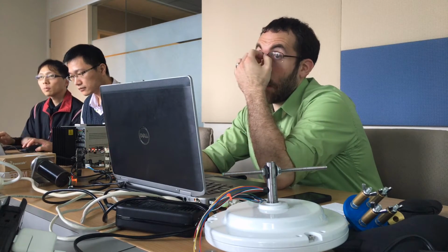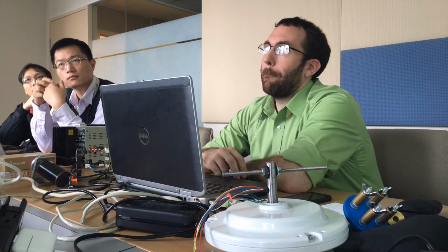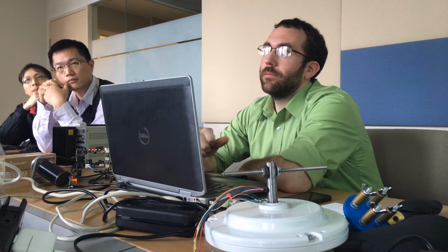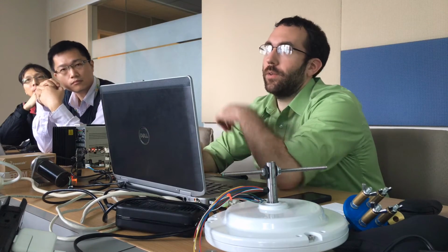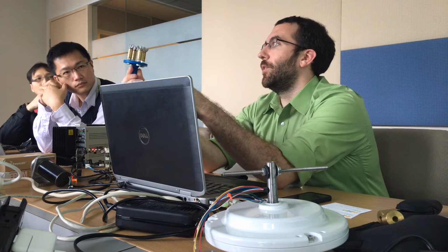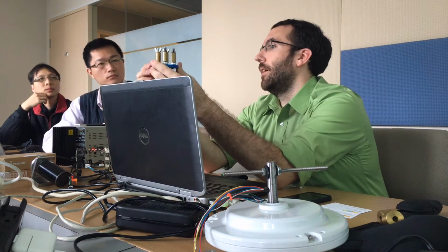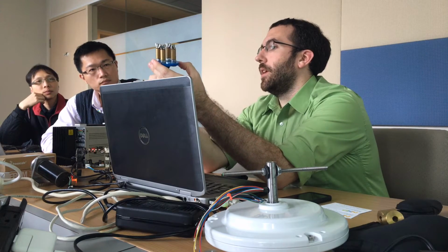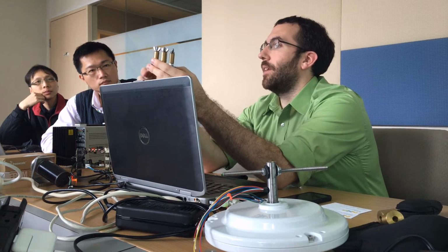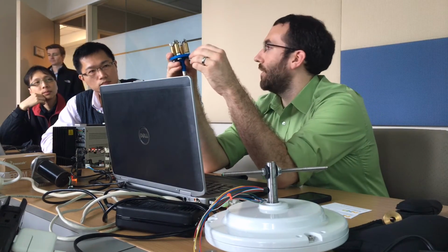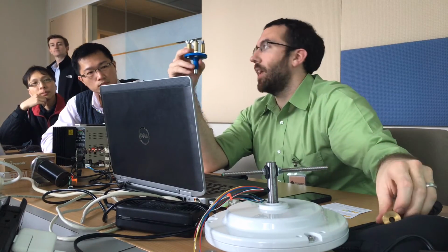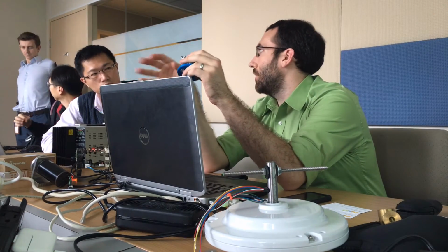Some of the benefits I was trying to demonstrate yesterday was the load sensitivity on position control. We have the ability to manage a load up to an 8x differential. It's actually inertia. If I've got this little inertia disc here where I can take these weights on and off, the controller is good enough to handle taking these weights off and dropping the inertia by half, then putting the bigger weights on and making the inertia twice as big as the setting, and it's the same level of performance without retuning anything.